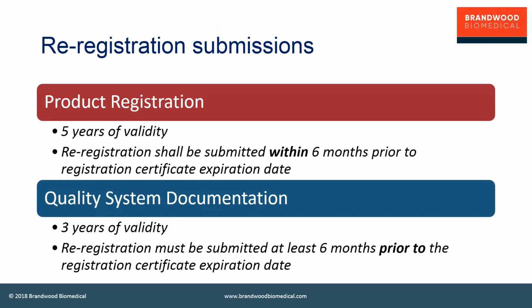Registrations have to be renewed, and as I said before, the QSD is on a 3-year renewal cycle. The product registration is on a 5-year renewal cycle, so they do get out of step. A product registration is granted for 5 years, and again, the re-registration needs to be submitted within 6 months prior to the registration certificate expiration date. Not more than 6 months, but within that 6-month period, you need to file the registration certificate renewal. The QSD has 3 years of validity, and the re-registration must be submitted at least 6 months prior to the registration certificate expiration date. So you need to manage your calendars and not forget to get back to the agency with appropriate renewals at the right times. Otherwise, you'll find that you've got lapses in registrations or QSD certificates, and you have to start all over again.